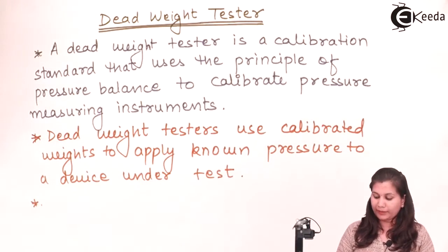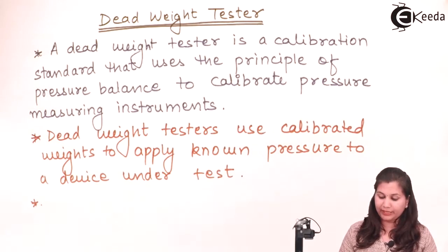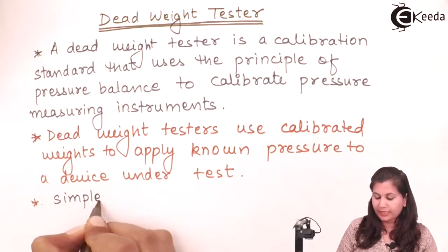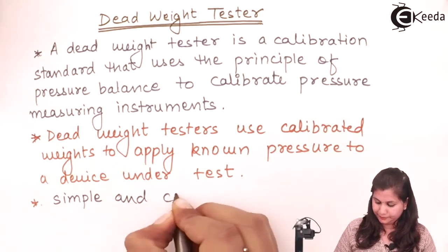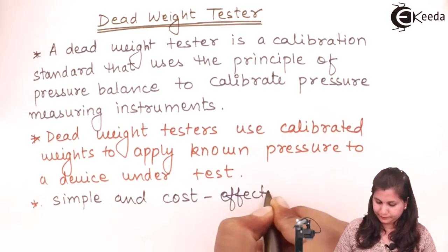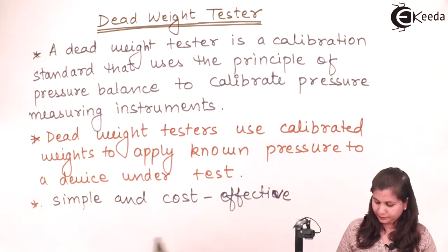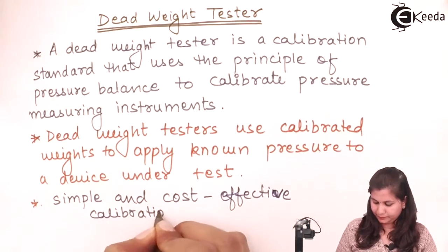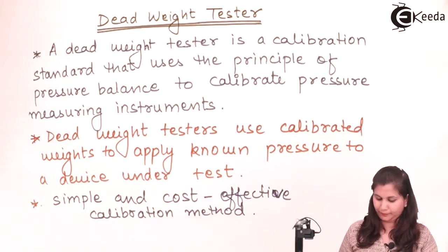So it uses calibrated weights to apply a known pressure to a device under test, and this type of calibration method is very simple and cost effective. Now these deadweight testers are an assembly of a piston and a cylinder. They are a type of piston cylinder type measuring device, and they are the primary calibration devices used for the calibration of pressure measuring devices in different applications, for electronic and mechanical instruments.